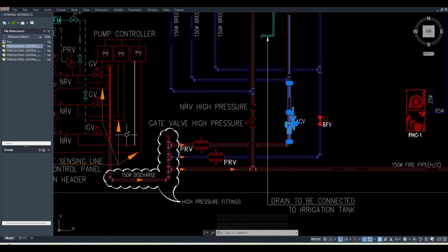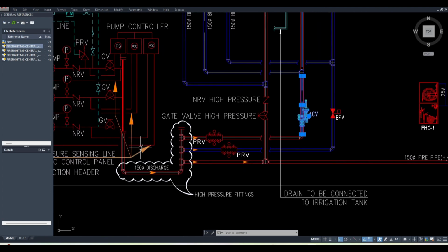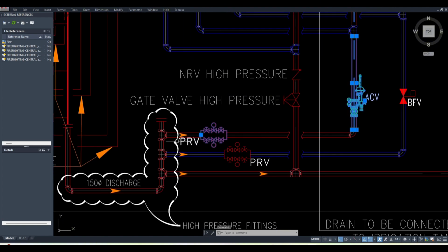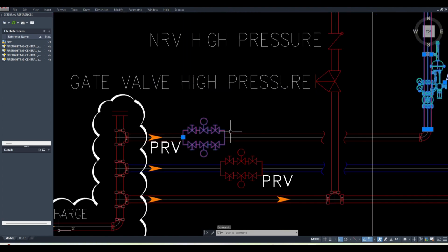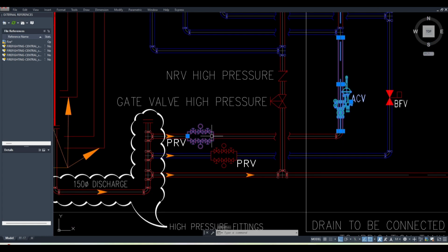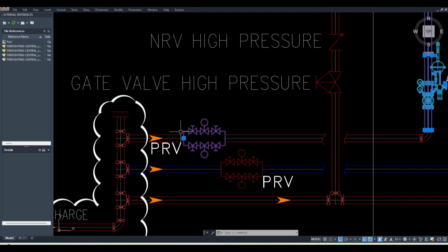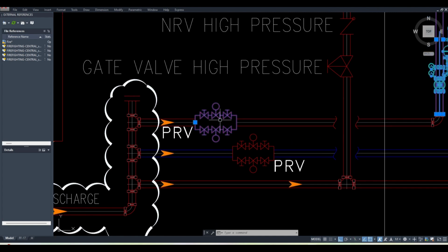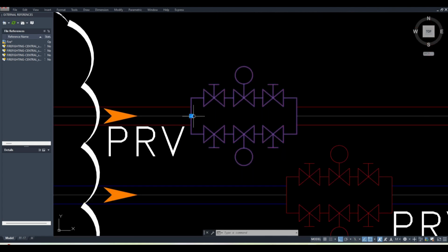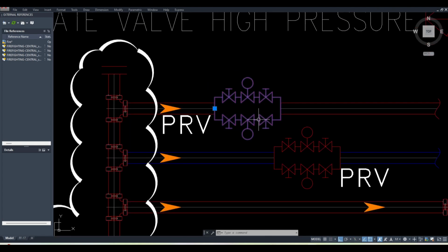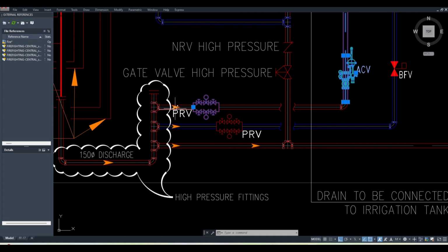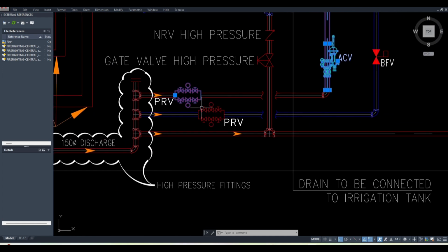So now when we see this system, first it is made with the PRV system, we call it pressure reducing valve, okay. So this is an assembly of valves again, the IV, and then in between the pressure reducing valve, okay. And this also comes with one working, one standby. So if you are doing maintenance on this one, this will be working, and if you are maintaining this, this will be working, okay.